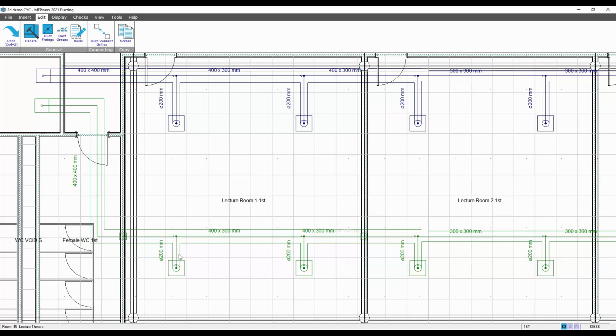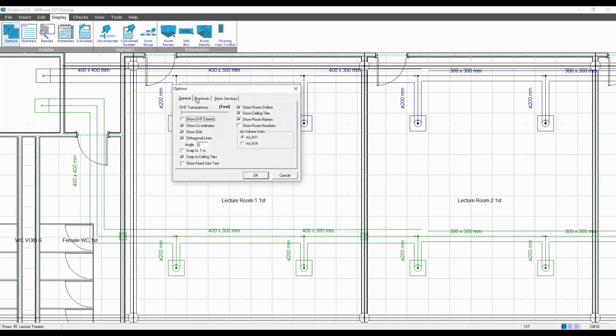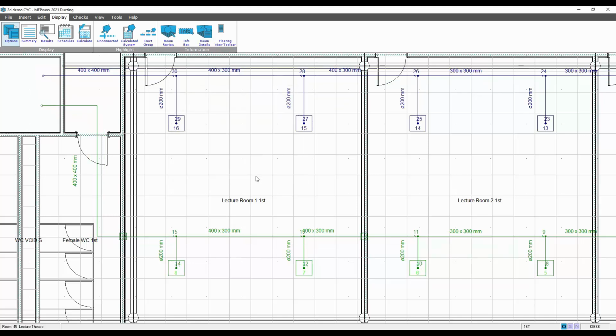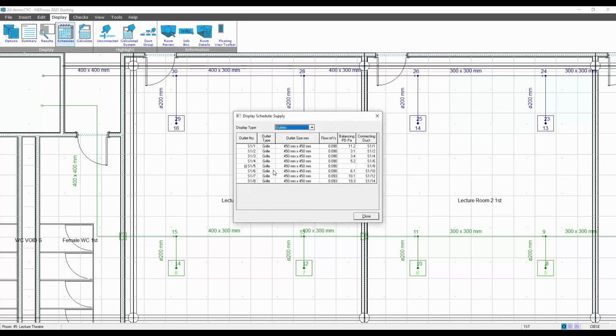To do this, I want to know the duct numbers, so I can go to display options and I can display on the ductwork duct numbers and grill numbers. I can then go to the display menu and select schedules on the supply system as the last calculated system. And then I can see the residual pressures required for the balancing at each part. So let's say, for example, I want to balance grill number 8, which is this one here.